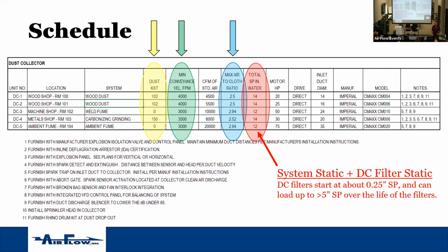Your initial filters through a media filter are going to start off somewhere around 0.1, 0.2, 0.25 differential. But it doesn't take long, and you're going to load up to about 1 inch to 1.5 inches, and you could run at that for a very long time. If you have a shaker or a pulse cleaning system with compressed air, it could hover around that 2 to 3 inch mark for quite a while. It'll climb to 4 to 5. A lot of times they'll tell you that you don't need to change at 5 inches. Order yourself some new filters and get them on hand. When you run to the point where your pulse cleaning can't clean off anymore and can't drop that differential pressure, then that's the time to change your filters.